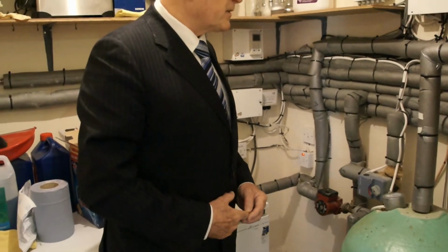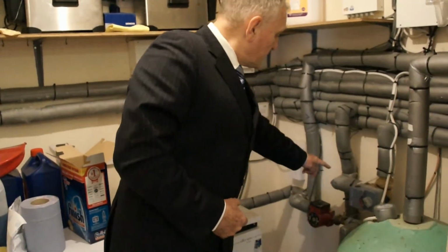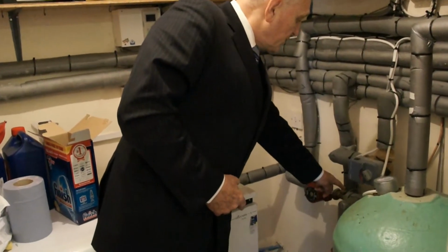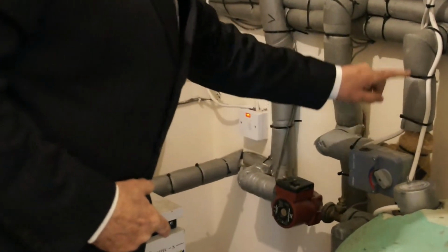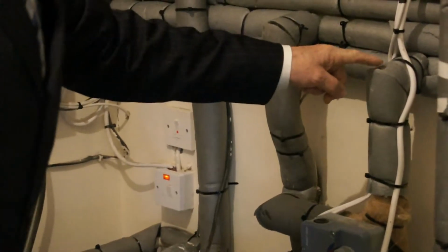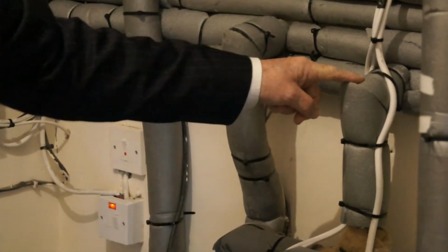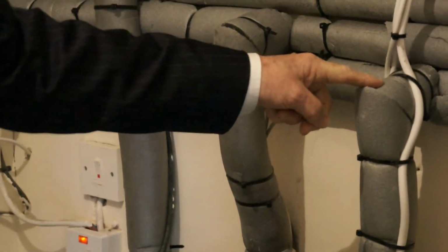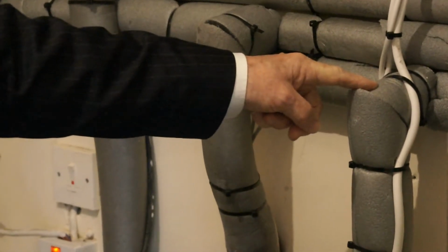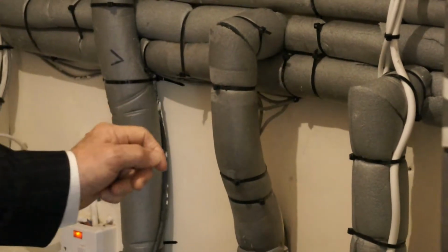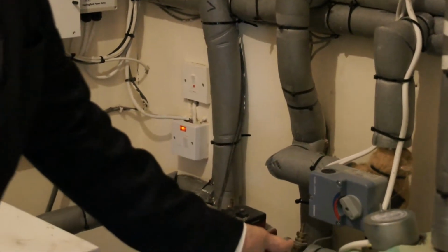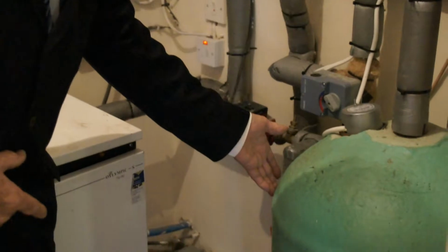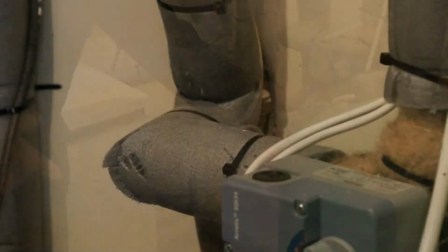So to minimise that effect, what we want to do is take this hot water at 75 degrees and reduce the flow temperature for the heating only to 50 degrees, and in the case of something like underfloor heating it might be as low as 25 degrees, whilst at the same time being able to heat the hot water cylinder we have here to the 60 degrees required for hot water.